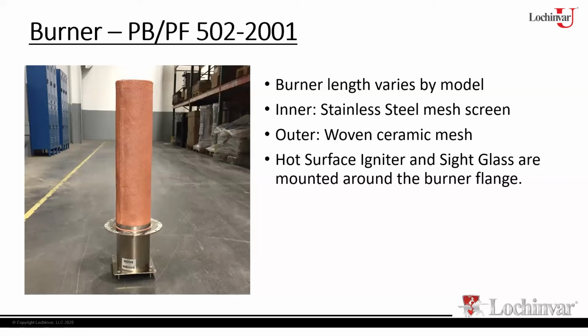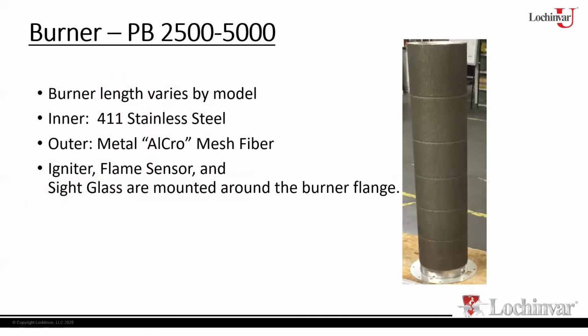So again, we want that balance from top to bottom all the way around. So we have ceramic fiber on the smaller models. Then we went to the larger models, the 2.5 to 5 million. We went back to the AlCro mesh material. This is pretty much the standard material that we use on all the other burners. The 500 to 2 million ceramic fiber burner is unique to that particular product. It's something that we wanted to try on it. Works well there, but again, for the larger models, we went back to something that we already had a lot more experience with, and that was the AlCro mesh material.